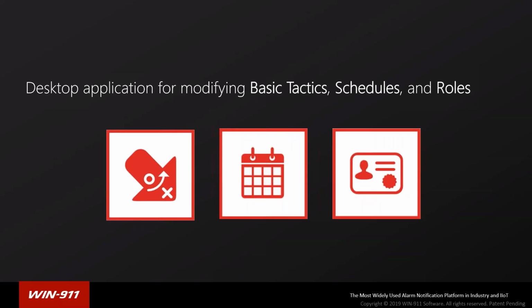So basically what it lets you do is modify your basic tactic schedules and roles. A basic tactic, for those who are unaware, is a call out list. So operators will be able to add or remove contacts from that call out list, as well as edit delays and retries. You can't create a new tactic or delete an existing tactic with the tool. For that, you would need full access to the WIN-911 workspace. So this utility is not for creating new call-out lists.